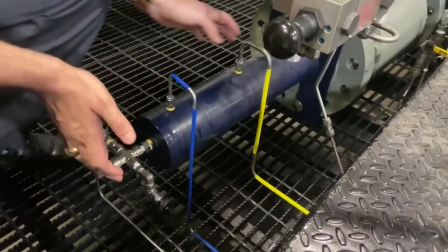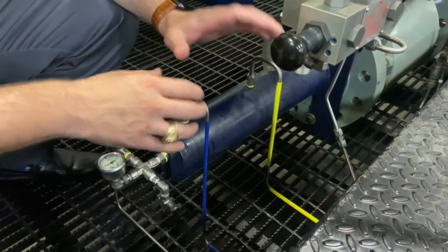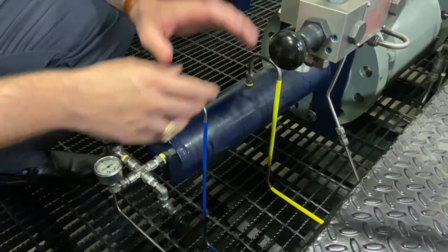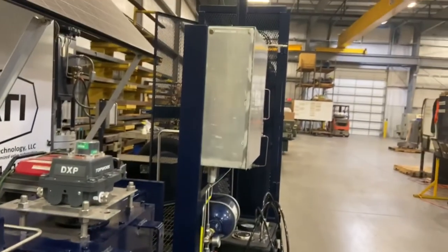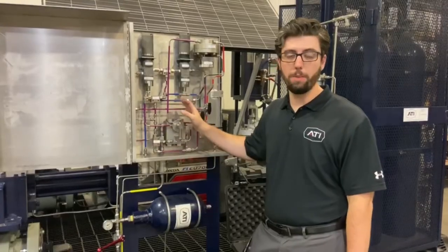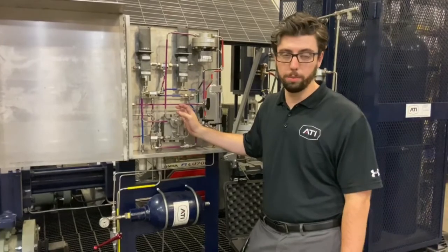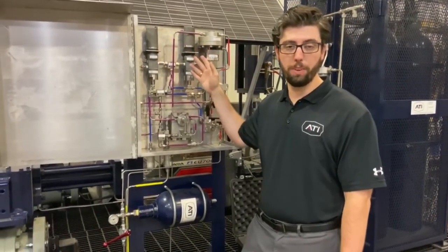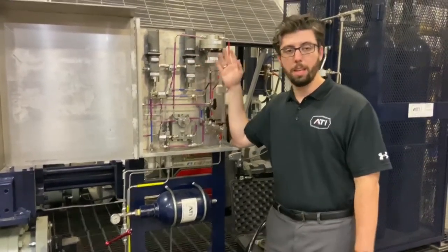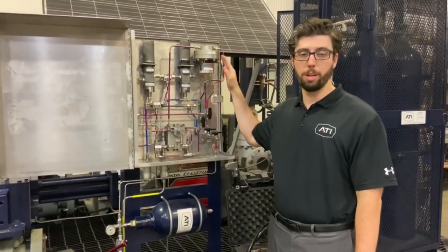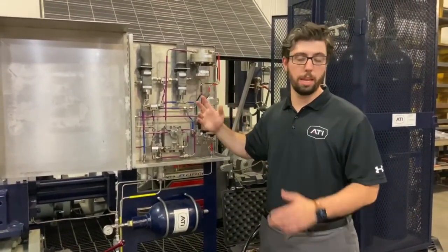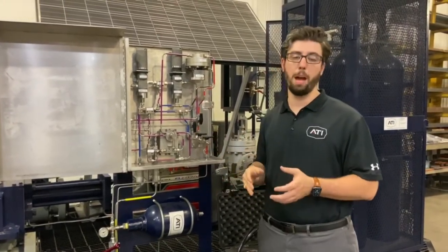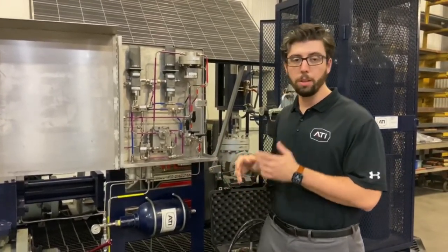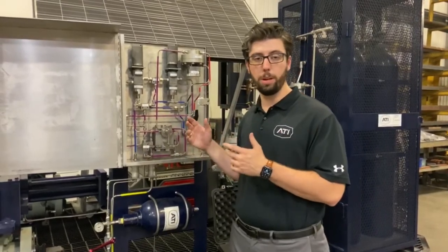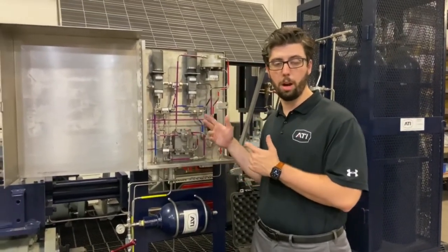And then down here, this is what simulates our pipeline, and we can do all kinds of different testing and show off the capabilities of our pipeline control system. We have a three-way poppet block for local control. We have high and low pressure trip valves for ESD of the pipeline. And then we have a differential pilot valve, which will sense either a break or a leak in your pipeline and shut the actuator.